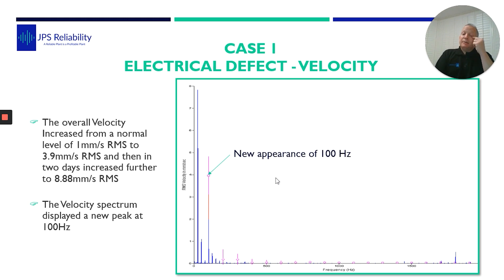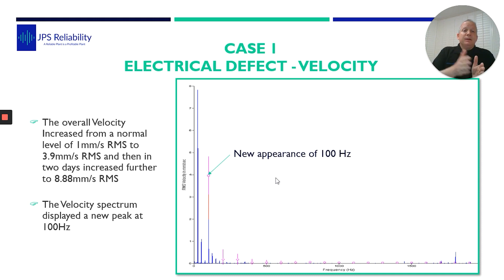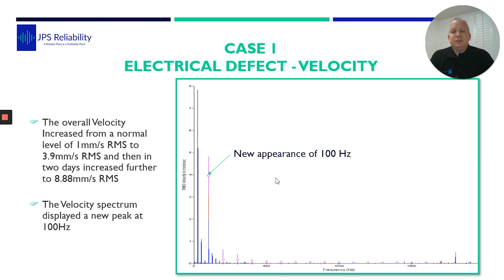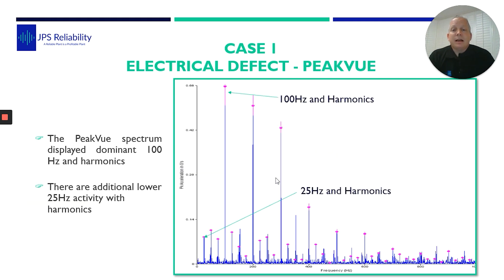We got called to this site and had some old historical data on this. It was about one millimeter per second RMS, then jumped up to 3.9 — which by ISO isn't bad, but there's a huge change in condition. We went back two days later and it was up to 8.8 millimeters per second RMS velocity. In between those two days, someone else had come in and done analysis and said the drive end was hot, suspected bearing — change the bearings. So we wanted to get more data behind our decision. We took some PeakVue data and found lots of electrical noise, which PeakVue does tend to pick up.